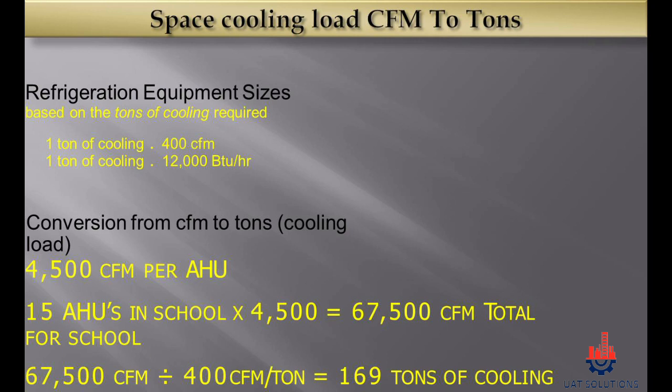The second step in conversion is to convert space cooling load CFM into tons of refrigeration, where 1 ton of cooling equals 400 CFM and 1 ton equals 12,000 BTU per hour. We are using 15 AHUs in the school building, each supplying 4,500 CFM, so 15 AHUs will supply 67,500 CFM as total space cooling load. Dividing 67,500 by 400, we need 169 tons of refrigeration for space cooling only.